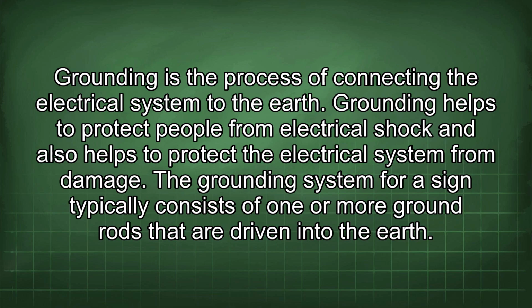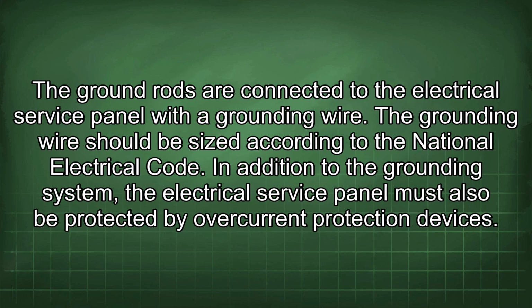The grounding system for a sign typically consists of one or more ground rods driven into the earth. The ground rods are connected to the electrical service panel with a grounding wire, which should be sized according to the National Electrical Code.